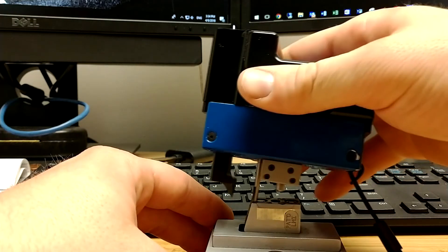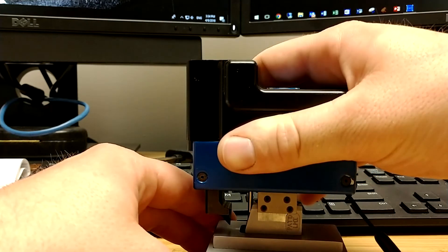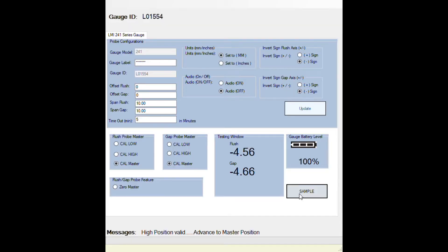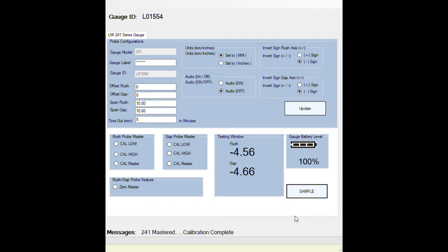For cal master, put it in your mastering block. Let it sit on a desk so you're not interfering with the gauge at all. Then click on sample again. Now you'll see your live reading screen changed to zero and your gauge is mastered.